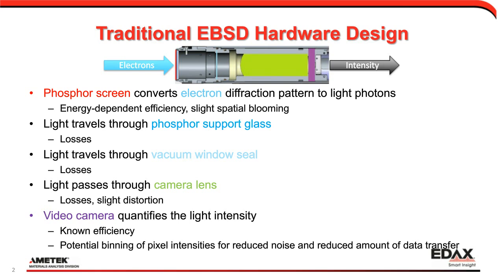These are the parts inside the system that you usually don't see, but they are very important for understanding the advantages and disadvantages of different camera systems. In the traditional method, electrons come in from the sample and hit a phosphor screen, converting them to light. That has an energy-dependent efficiency, and there can be slight spatial blooming or blurring from the actual location of incidence. That's the way phosphors work.